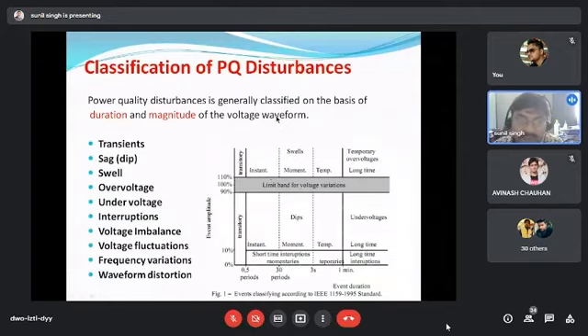Similarly, swells means if the voltage becomes above 1.1 per unit or approximately up to 1.8 per unit for a duration of 0.5 cycle to 1 minute, it is known as the swell. Now similarly, over voltage and under voltage, the same definition is there, but the difference is for the duration. If the sag, meaning the voltage dip, remains more than 1 minute, then it is known as the under voltage.